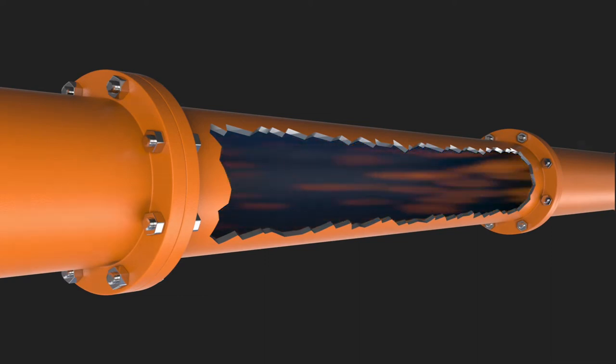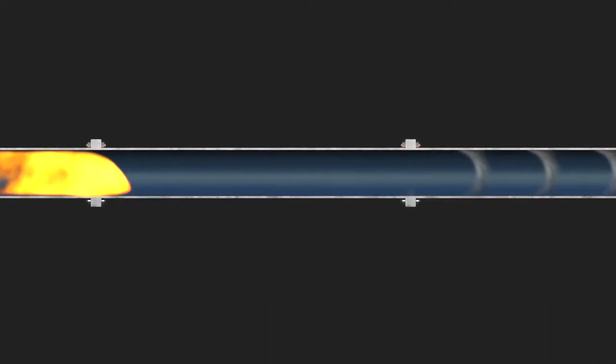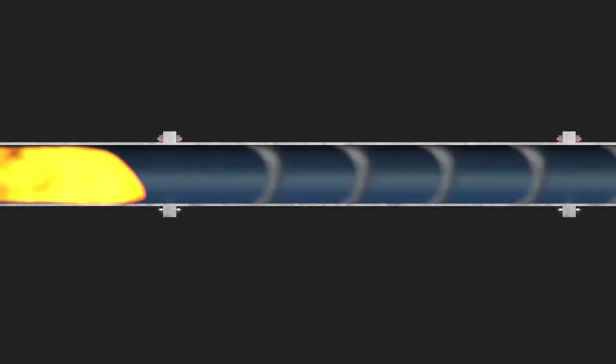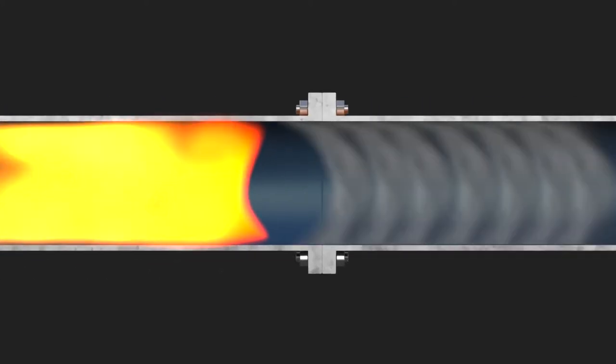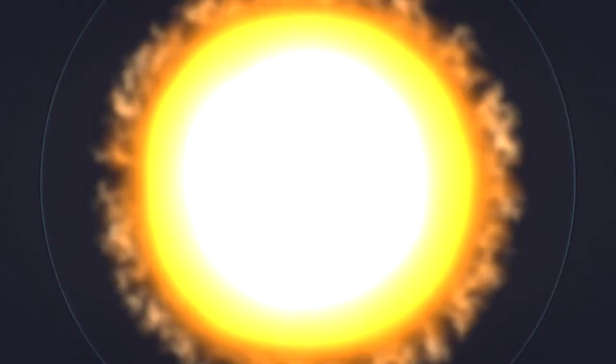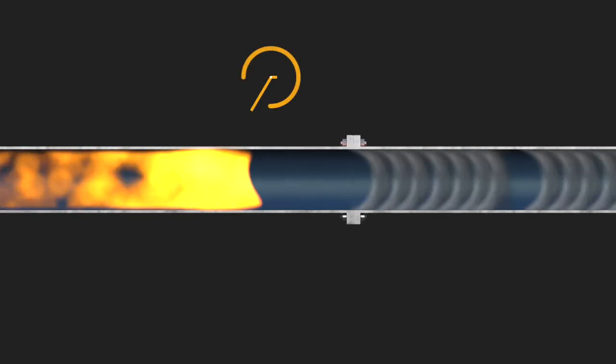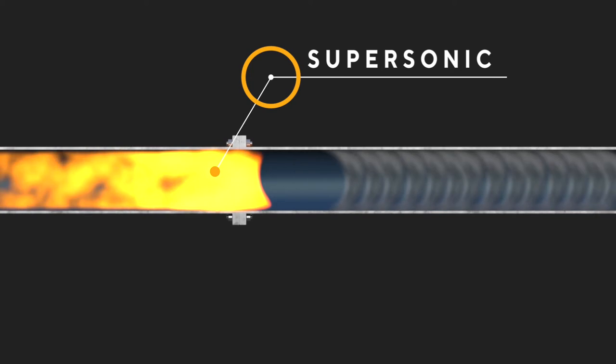This deflagration to detonation transition, often referred to as a DDT, is characterized by supersonic flame speeds in the range of 1600 to 3000 meters a second, and a shock wave that is now coupled to the flame front, creating enormous peak pressures.